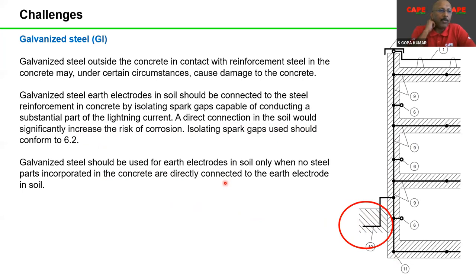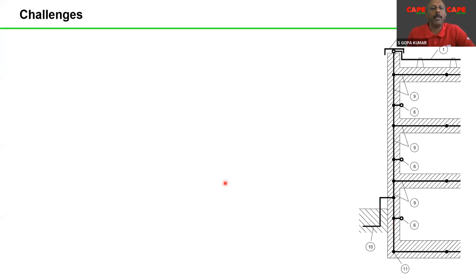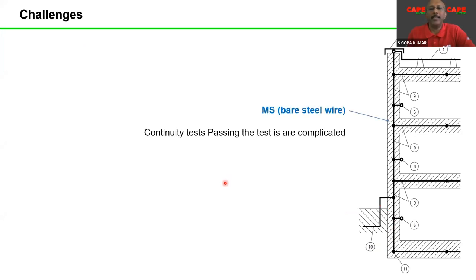Why I am very specific in this particular case is that whenever we design, people always try to mention that we should use GI because GI is cheap. Use MS because MS is cheap. So for GI, these are the challenges. In the other case, the first recommendation is that you use your MS conductor, the rebar itself. The standard says to use an additional conductor with a smooth surface. The second recommendation from the client is then that you use a bare conductor. That means you use a steel conductor, round, smooth surface, but without any coating.